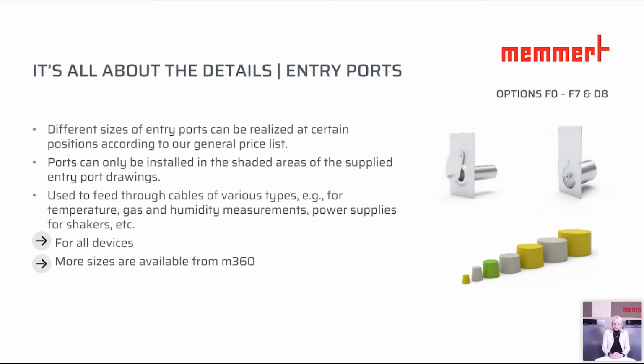The entry ports are always important in order to have this feed-through to put in cables, for example, if you want to do surveillance in regard to temperature with an additional sensor, or for humidity measurement, or for power supplies, for example, if you are going to use different devices like shakers. We have moisture-tight entry ports, for example, for our climate chambers. These are closed by silicone stoppers, which we can also see here in the pictures.